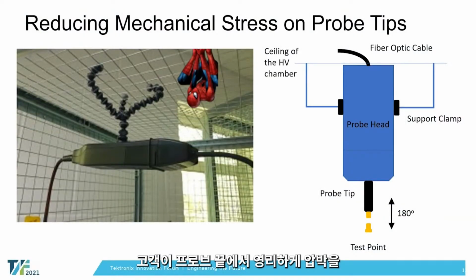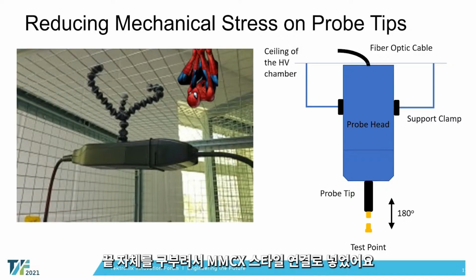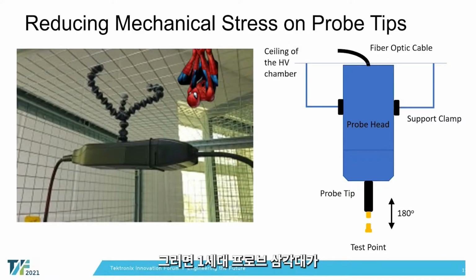Now, some of the ways that I've seen customers cleverly reduce the amount of stress on the probe tips are in two different ways. One is, there was a customer we worked with who had their test points on an angle, and rather than position the probe and then flex the tip itself into the MMCX style connection, they hung the tripod for the generation 1 probe on the cage, or the high voltage enclosure around their device. And that allowed them to hang the probe tip up there and then connect at a perpendicular level into the PCB board and the connection point.